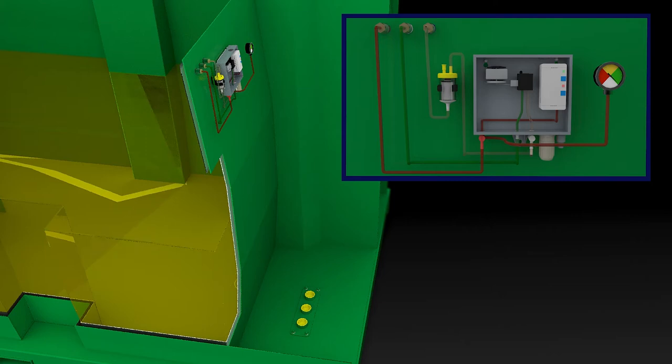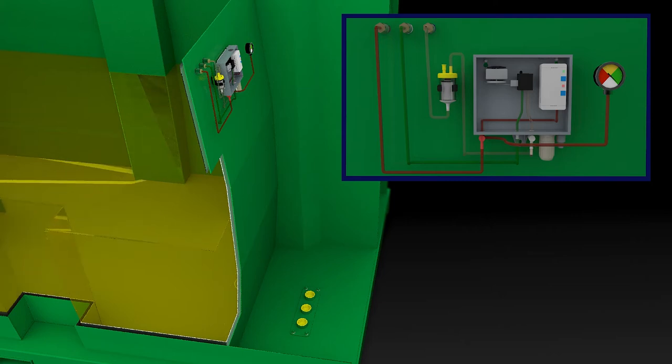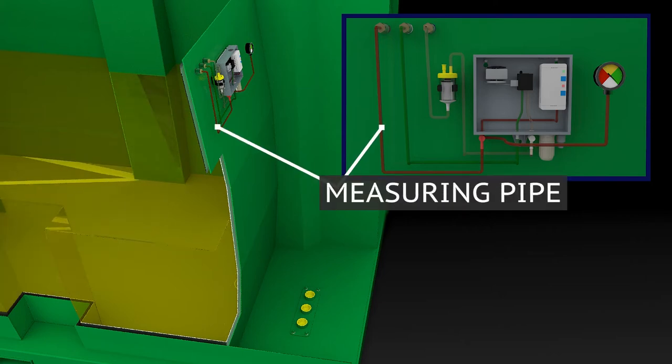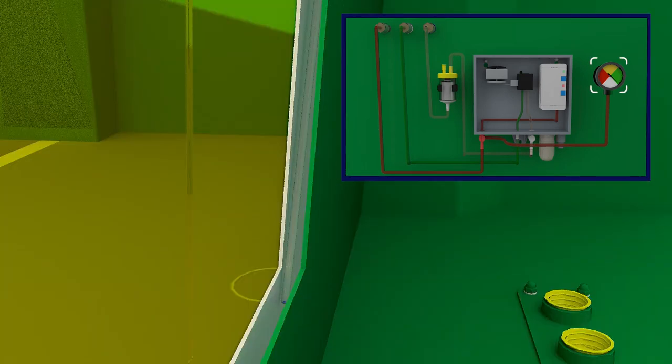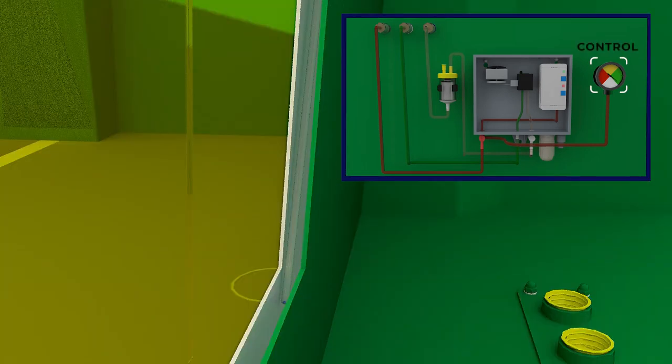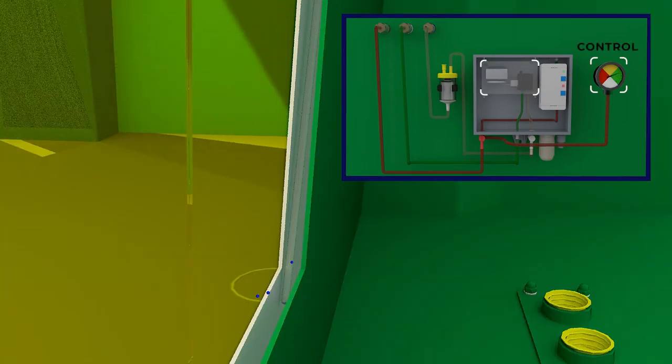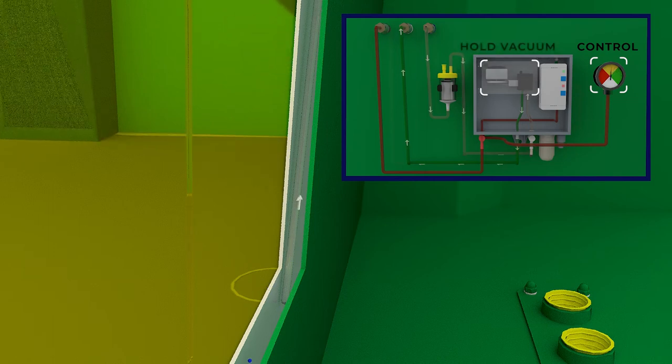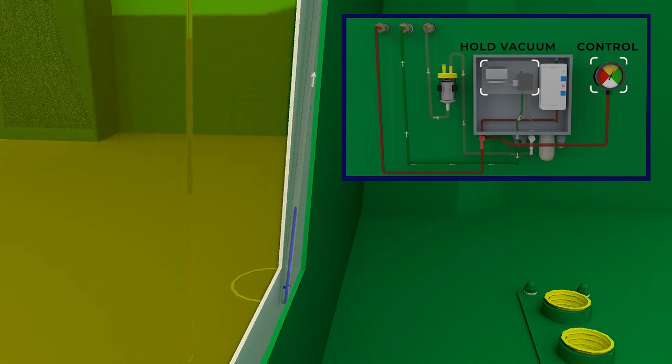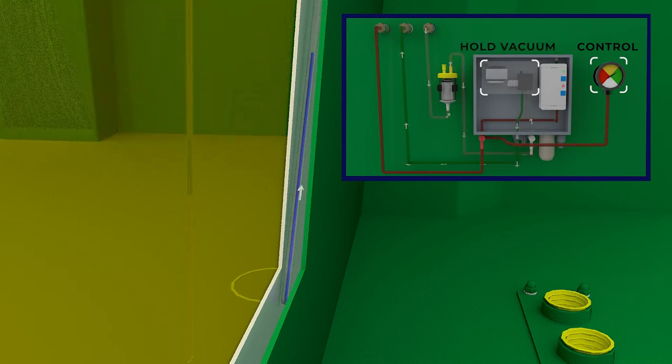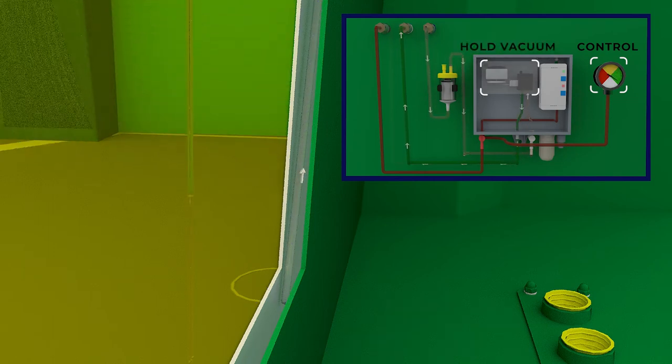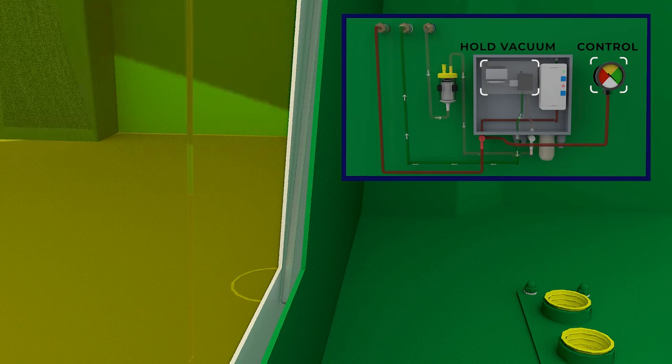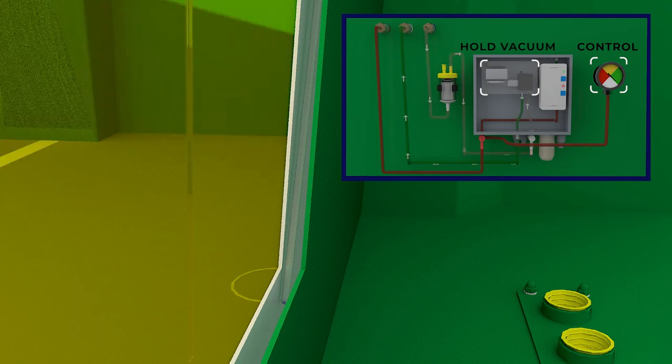Negative pressure, the vacuum, is continually checked by the measuring pipe. The vacuum pump starts every now and then in order to keep the vacuum constant. This is necessary, as a small drop in pressure in the vacuum system cannot be avoided over a longer time period.